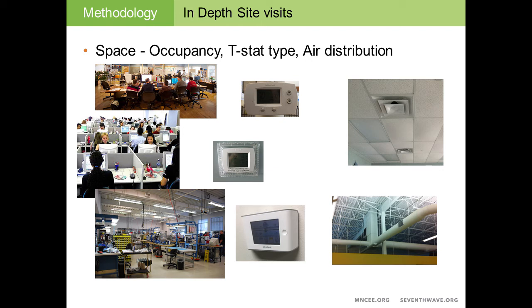The rightmost pictures are documenting the air distribution within the site. We wanted to know what type of air distribution was happening within the site. Do we have a false ceiling with a return air plenum, or a suspended ceiling, I should say, or do we have an open ductwork? So these are the types of information that we collected.